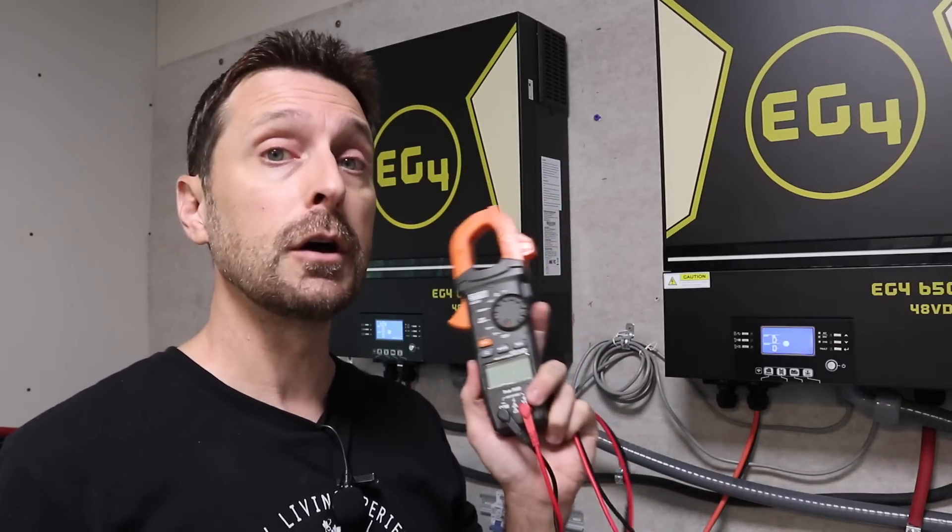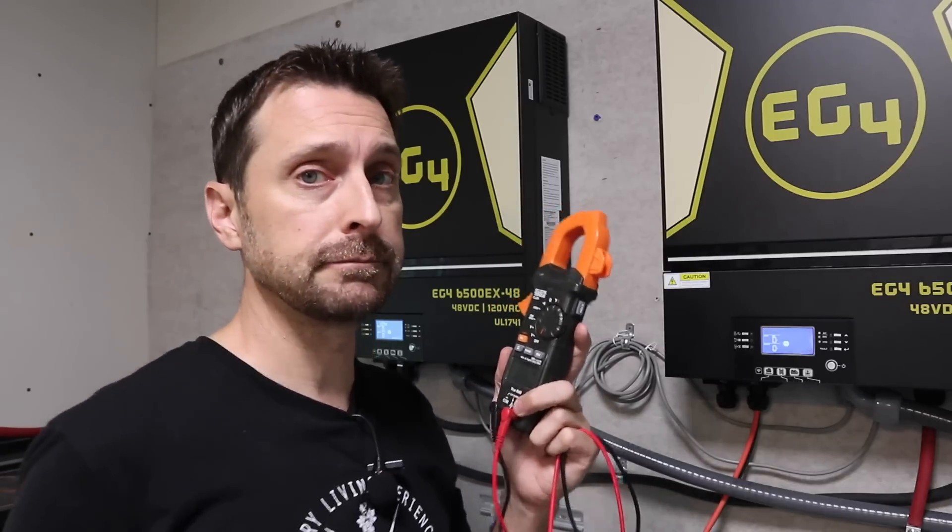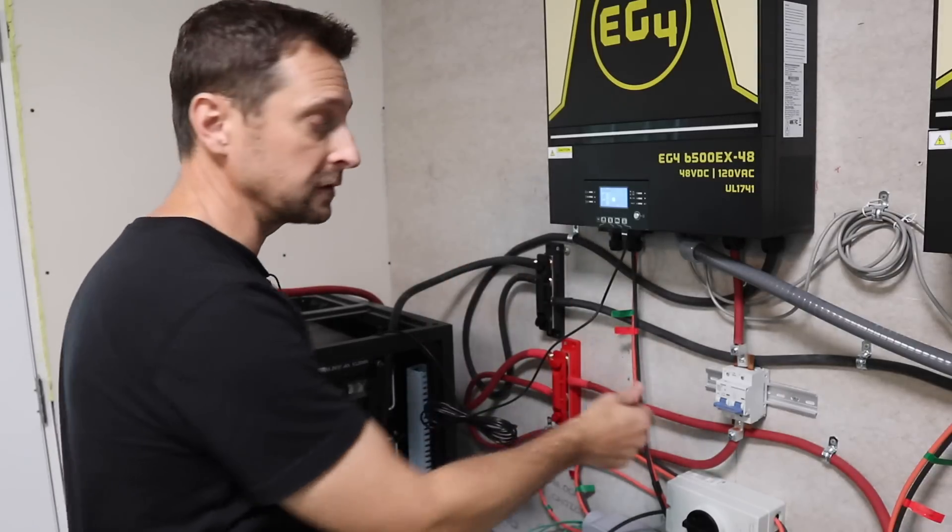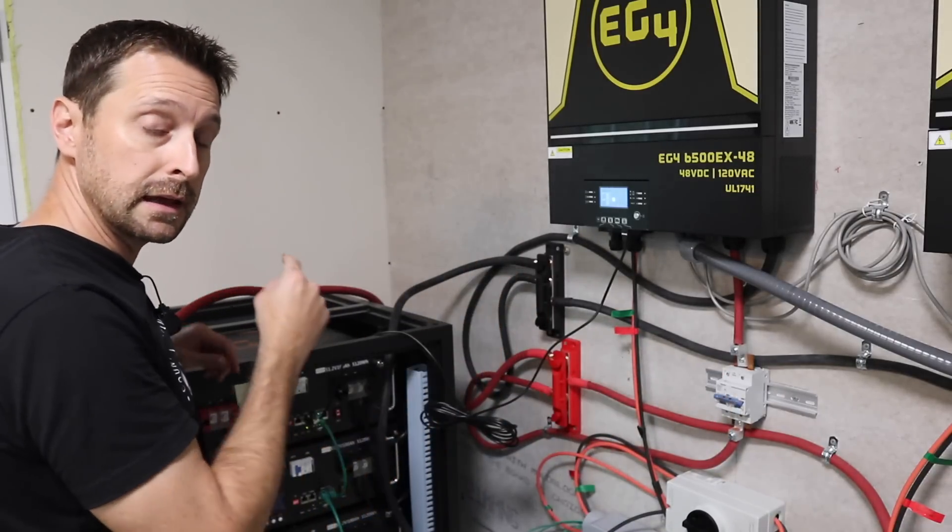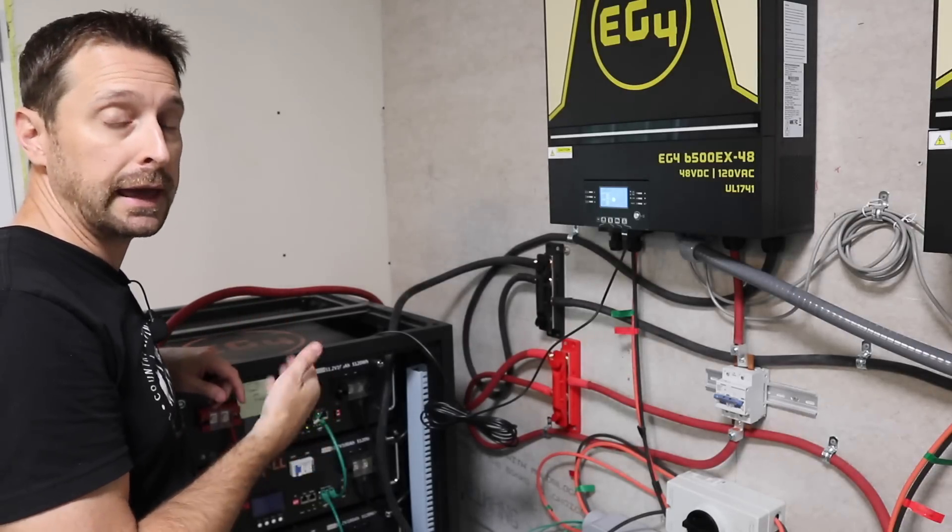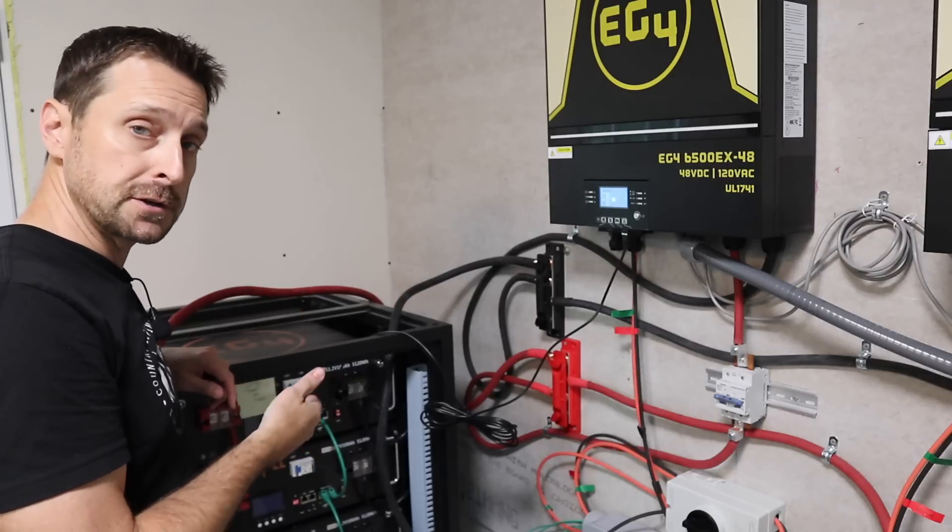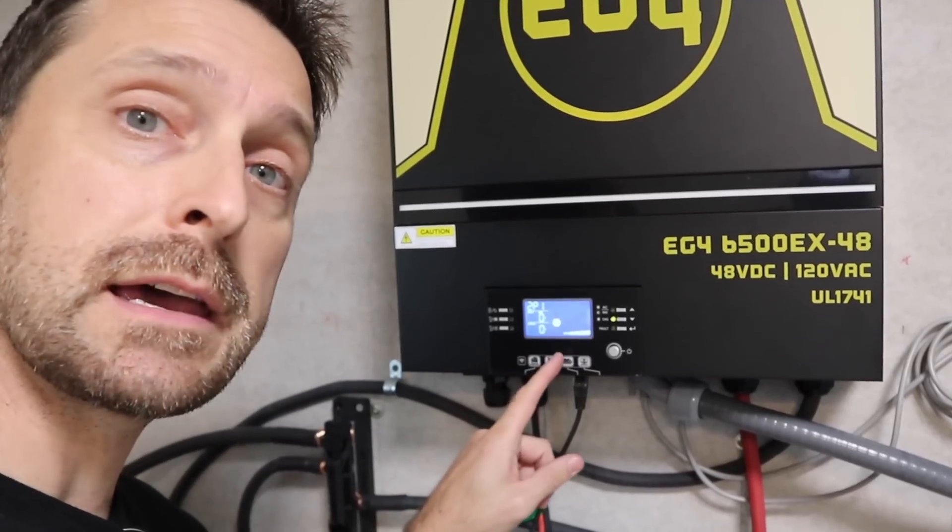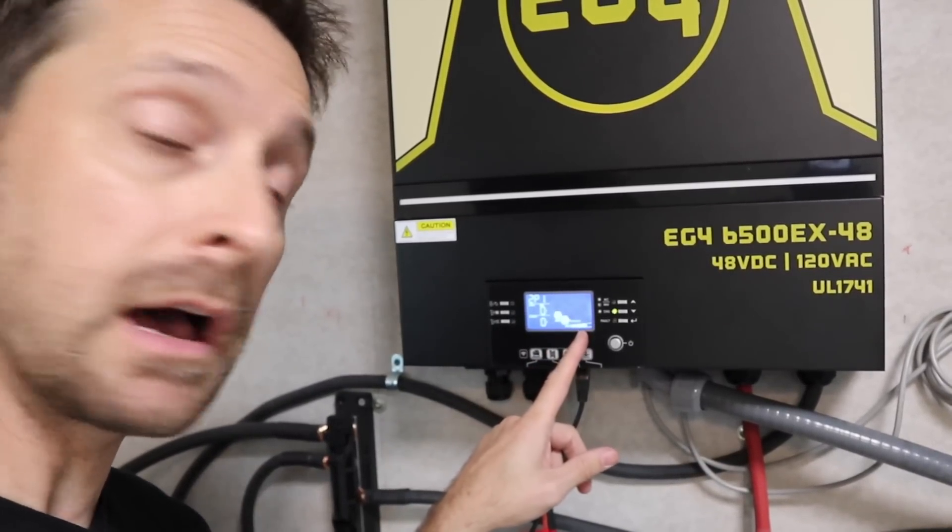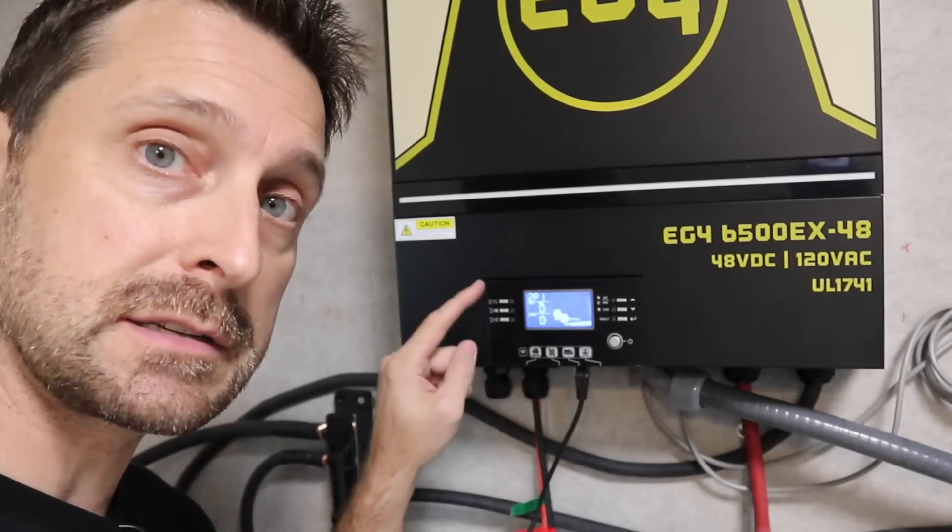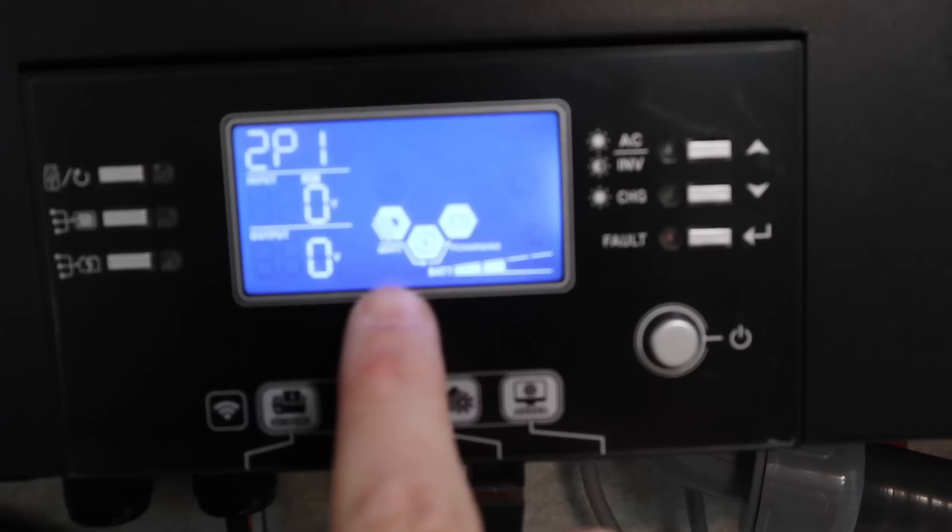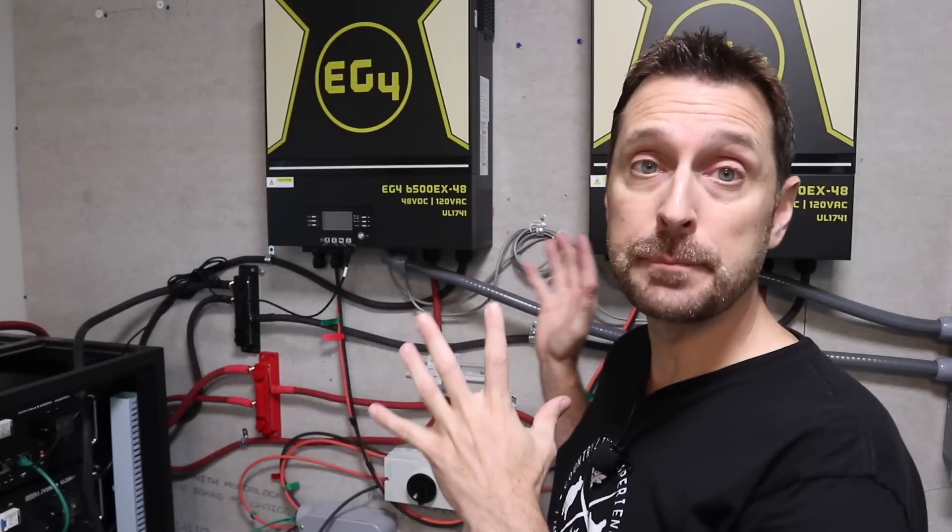Now I'm going to turn our batteries on and the first thing I need to do is turn on our external breakers and then I am going to turn on our battery breakers. Each battery has its own pre-charge resistor inside and built in. Once I did that, you can see that our battery is indicated as being on right here and that fault has disappeared. You can see it indicates the batteries are charging.